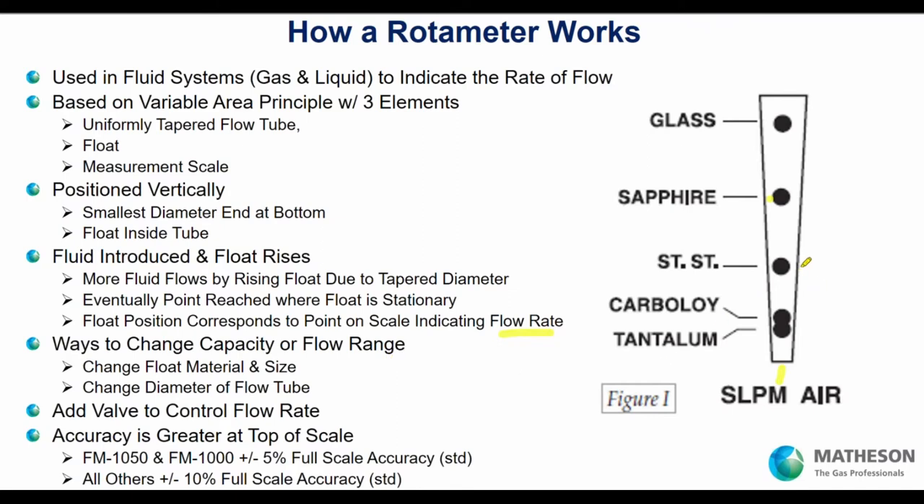How do you change the flow rate on a rotameter? You do that by changing your float — either the material or the size — or you can change the diameter of the tube, which you do with the mandrel and forming the glass around it. To set a specific flow rate and control flow to the point of use, you put a valve in and make sure that float stops at the desired position — for example, 6 liters per minute.